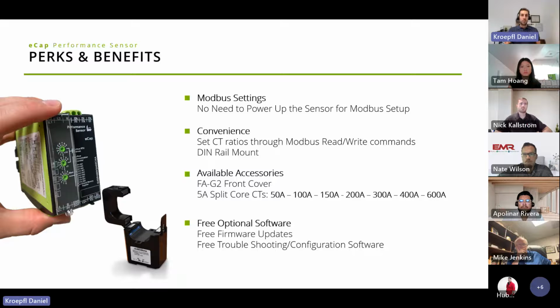What you can do is read in or write through the Modbus commands what current transducer ratios you want in place. That's very important, because if you have a customer running a larger quantity, you can't expect them to wire up or hook up every control panel two or three times during production. Ideally, they have one testing of the panel, then power it up, read in the values, select with their PLC what CT values they want to put in, and they're pretty much good to go - saving time and effort when it comes to programming that sensor.